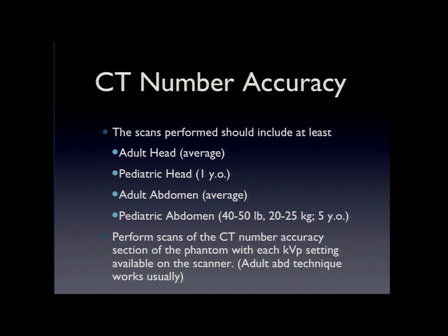Because if patients are done using auto mA, the mAs is going to be different depending on the size of the patient. And so you just look at what is the average patient size for this demographic, and just enter that, something similar to that, to do an evaluation. But one of the keys is, if you're doing it ongoing, you should use this same technique over and over again. But just be mindful of if there's any changes in their protocols.